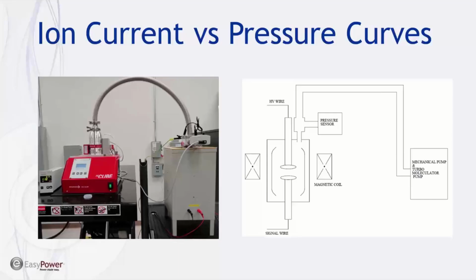through experiments like you see here, where we have a vacuum interrupter with a vacuum fitting welded onto the end cap. We have a pressure sensor and some insulation so that we can apply the high voltage to the vacuum interrupter while it's being pumped by, in this case, a turbomolecular vacuum pump. So we pump the vacuum interrupter down to a known pressure. We perform this magnetron test on it, and we get a current measurement. So as the pressure changes, the current measurement changes, and we can record these values, and after the experiment we can generate a curve, which is what we call them, of this ion current versus pressure.